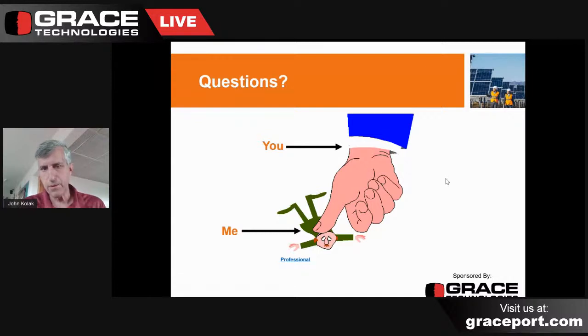So again, the relay coordination study is about everything tripping out in the right sequence. The arc flash part of that is we're interested in lowering the incident energy. So from an arc flash standpoint, I'd be happier with a miscoordinated system that trips out and gives you lower incident energy as long as the net result in the system is the same. So that's the difference. The relay coordination study is proper sequencing. The arc flash study is mostly interested in lowering incident energy. That being said, a home run would be if you get both. If you can have it sequenced properly and give you low incident energy, well, of course, that's a home run if we can do that.